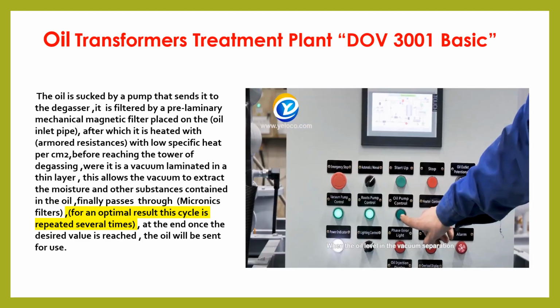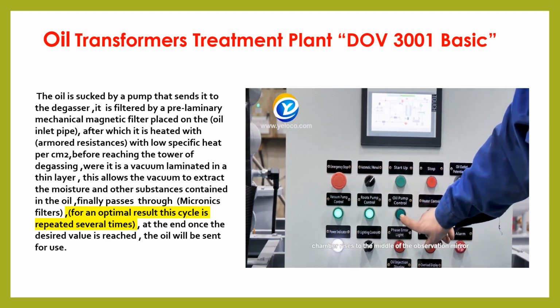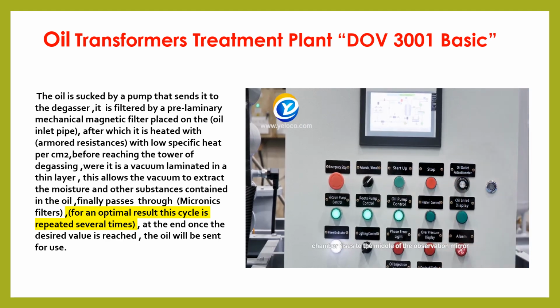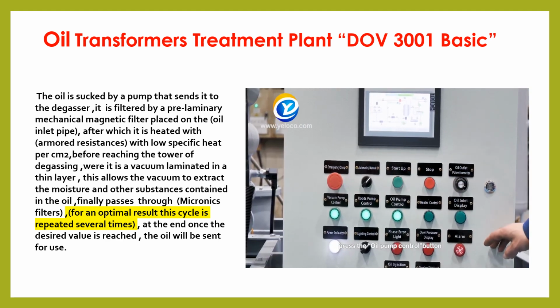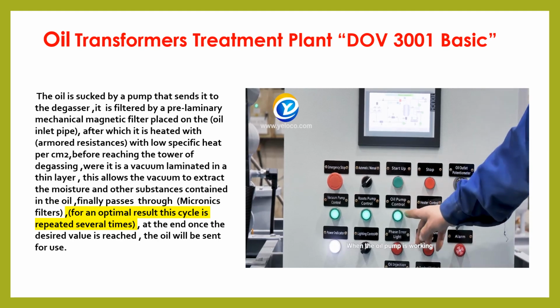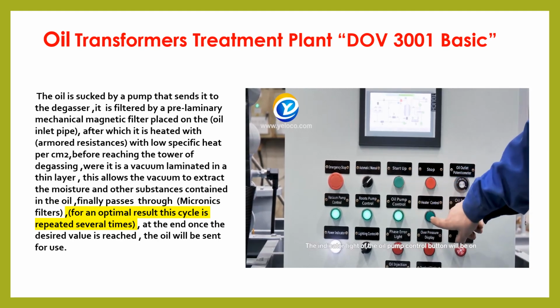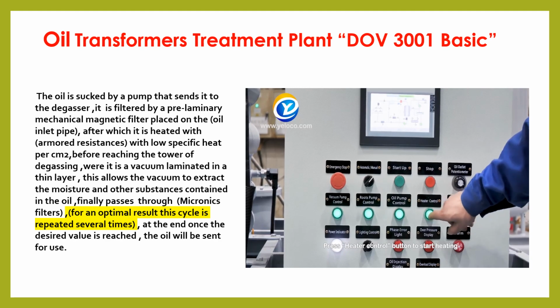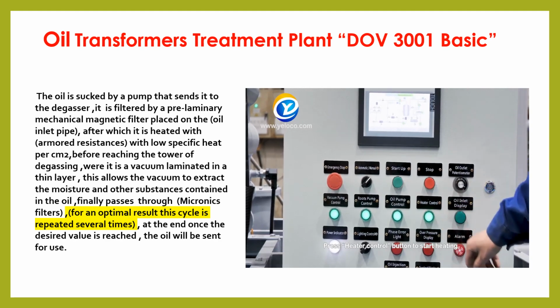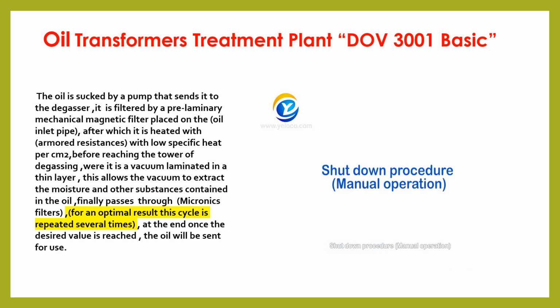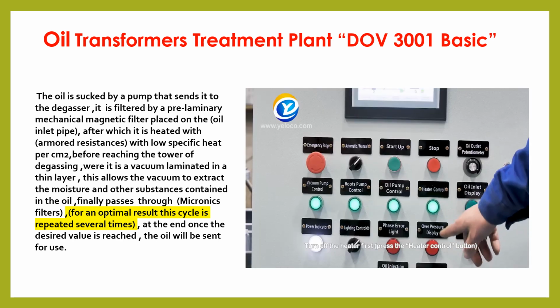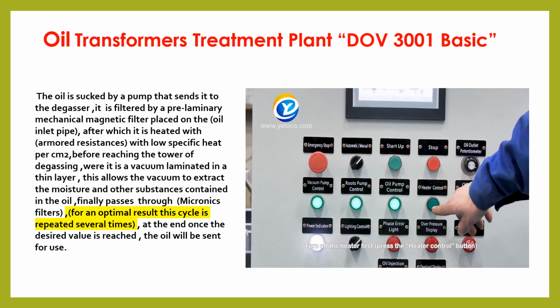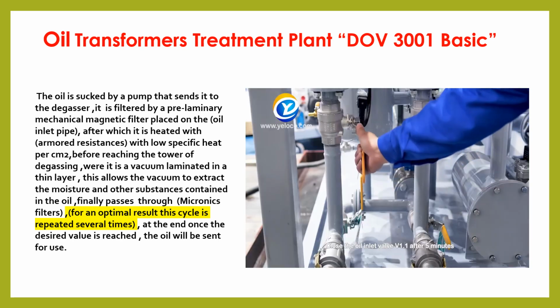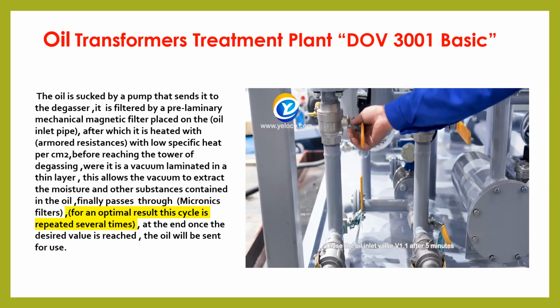When the oil level in the vacuum separation chamber rises to the middle of the observation mirror, press the oil pump control button. When the oil pump is working, the indicator light of the oil pump control button will be on. Press heater control button to start heating. Shutdown procedure, manual operation. Turn off the heater first. Press the heater control button. Close the oil inlet valve V1.1 after 5 minutes.